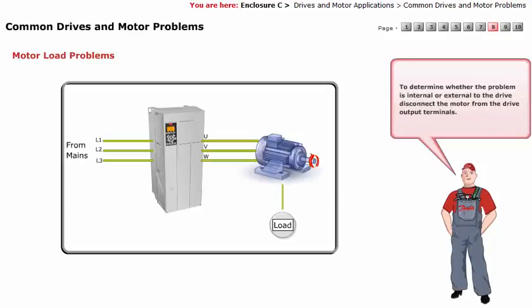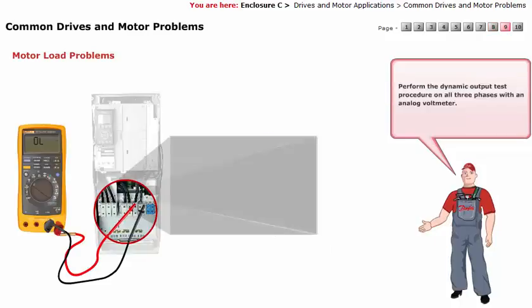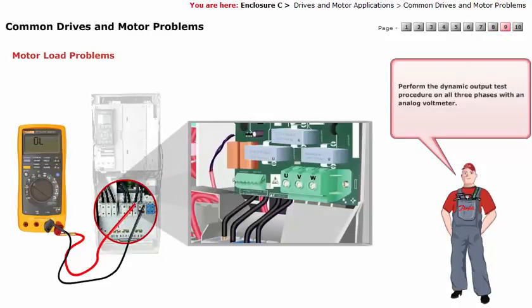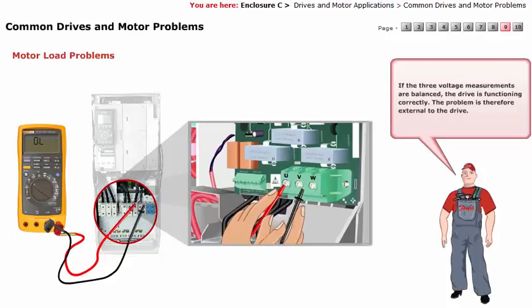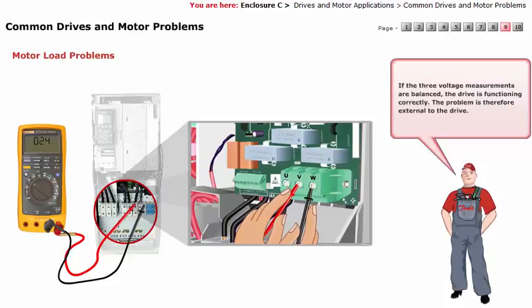To determine whether the problem is internal or external to the drive, disconnect the motor from the drive output terminals. Perform the dynamic output test procedure on all three phases with an analog voltmeter. If the three voltage measurements are balanced, the drive is functioning correctly, and the problem is therefore external to the drive.